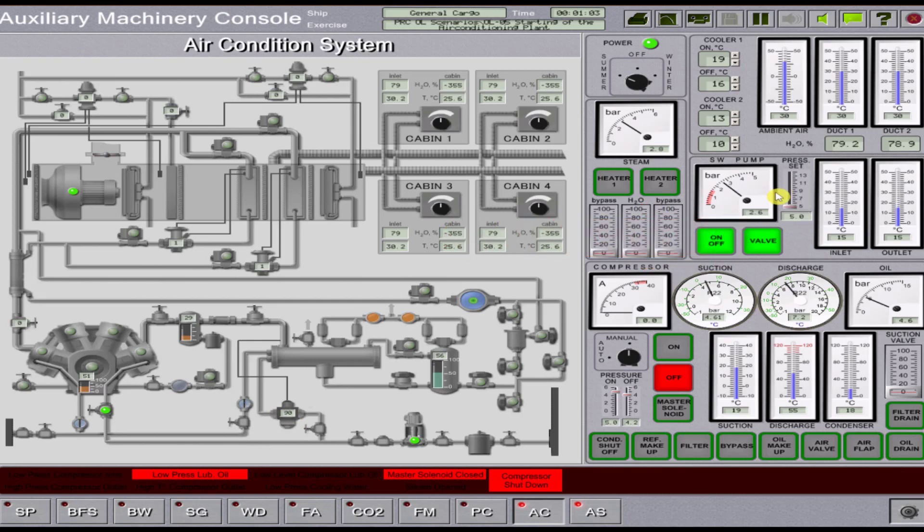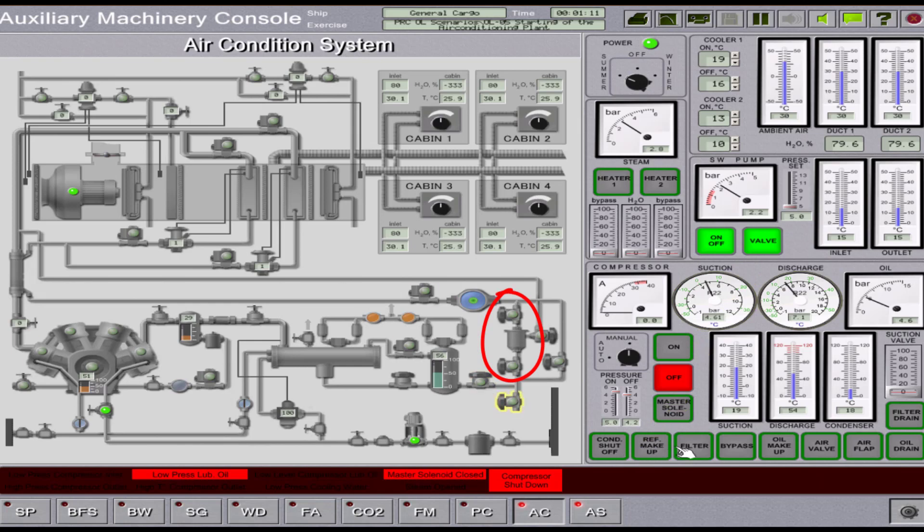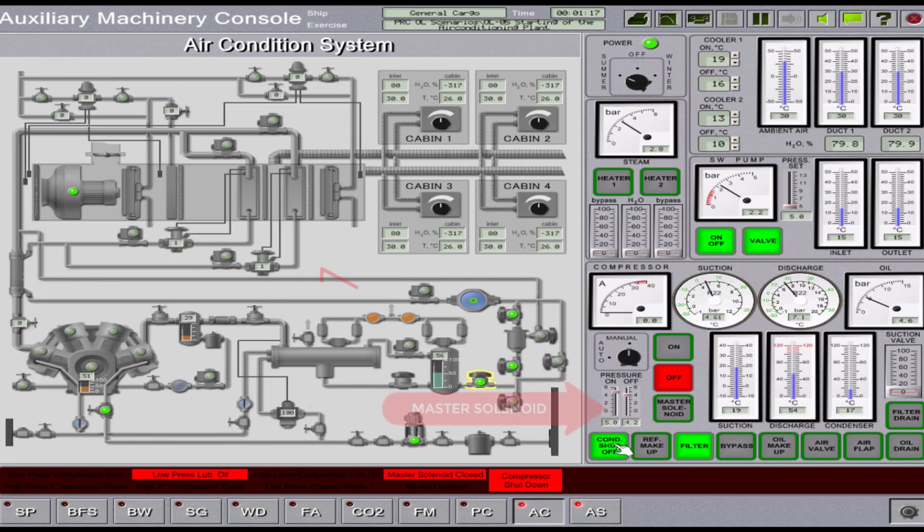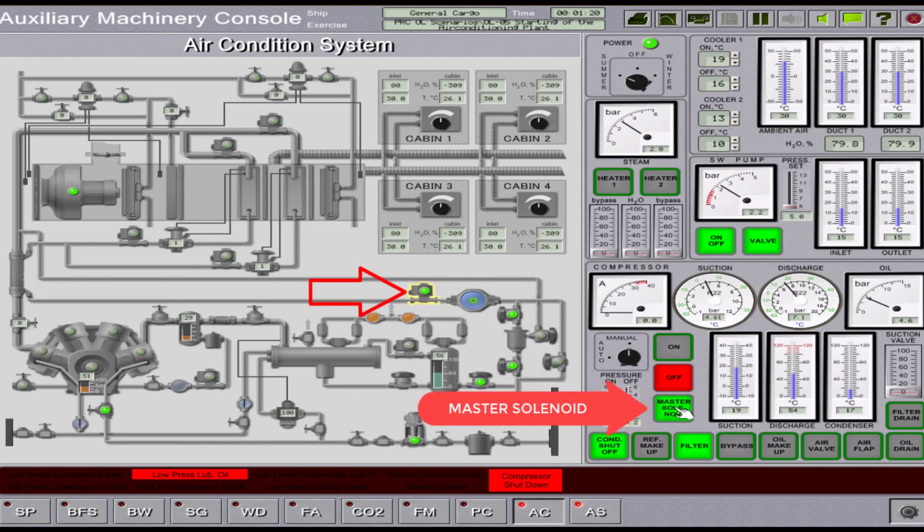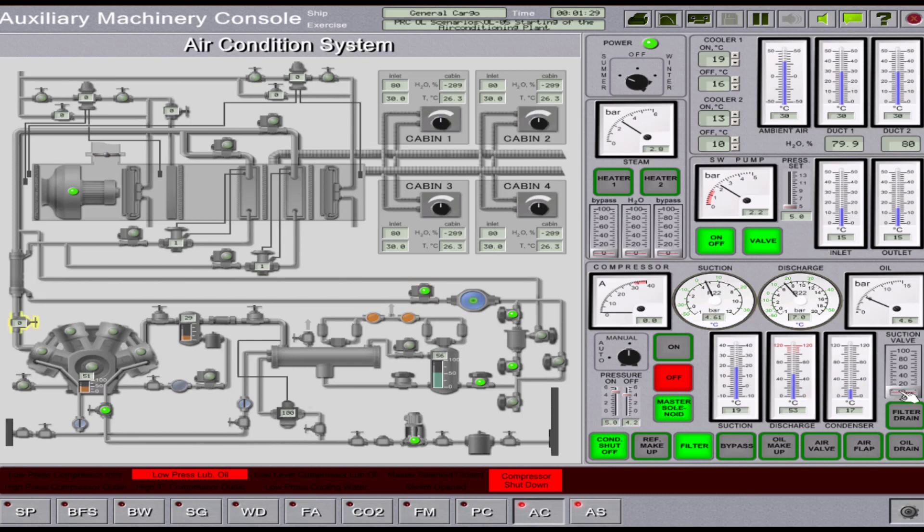After you have completed it, open the shut-off valves on the liquid refrigerant circulation lines, that is the filter and condenser shut-off. Then, manually open the master solenoid valve. Once you have opened those valves, check the compressor suction valve if it is closed.